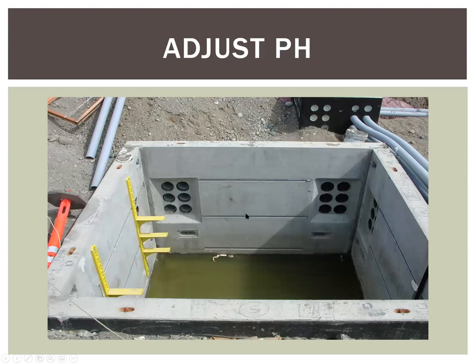If you are doing anything with concrete — cast-in-place or precast vaults — the water sitting in them will have elevated pH. A precast vault outlet might elevate to 9 or 9.5 pH; cast-in-place concrete could easily be pH 10 to 11 for some period of time. Before you can discharge that water, it needs to be treated. In Washington, and likely elsewhere, high-pH water cannot be put into groundwater. It would have to be treated with a mild acid — such as CO2 or citric acid — to bring the pH down to the typical acceptable range of 6.5 to 8.5.